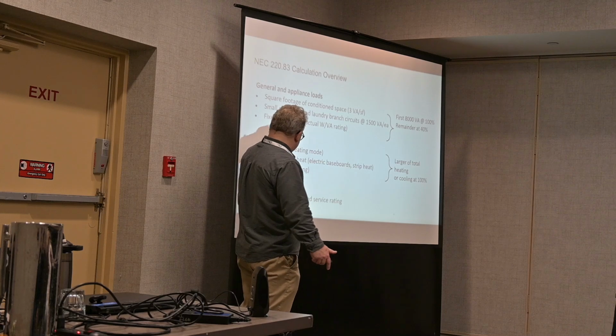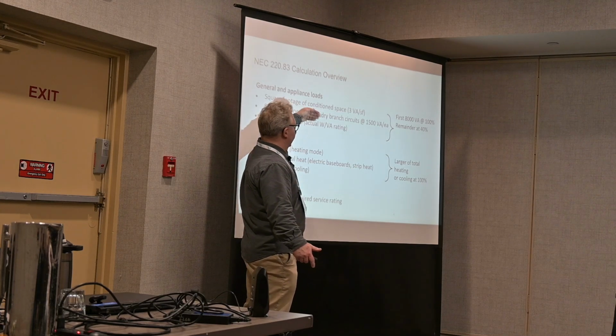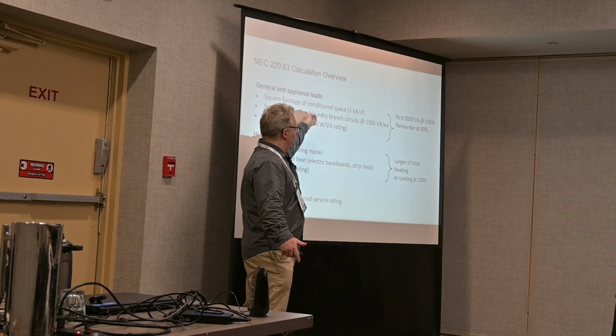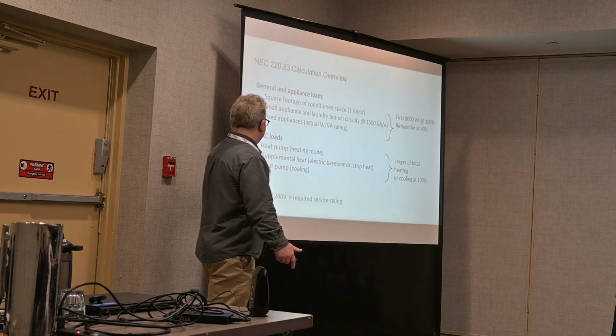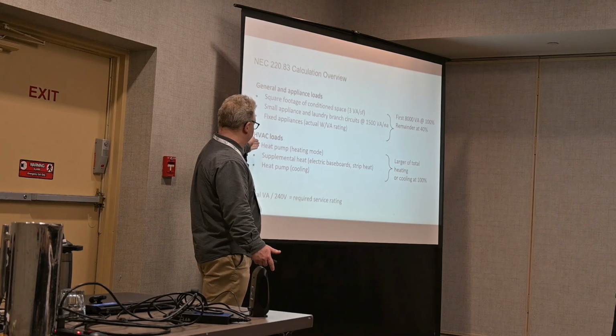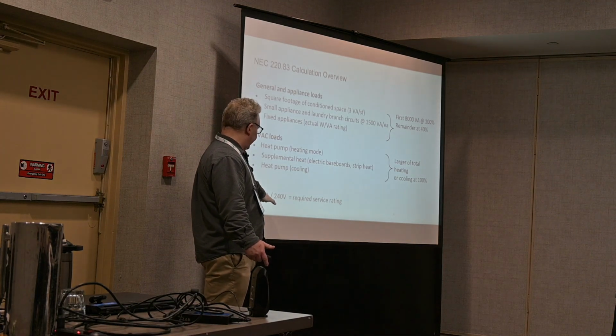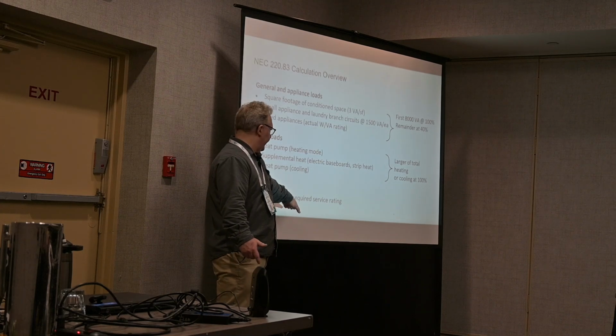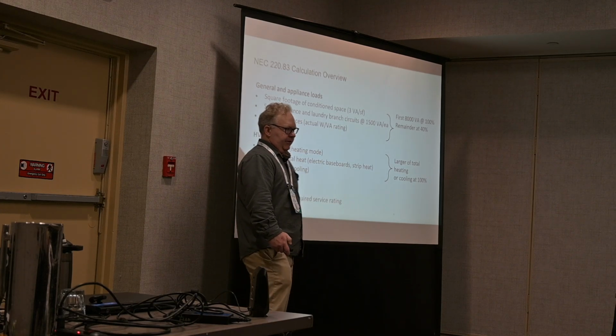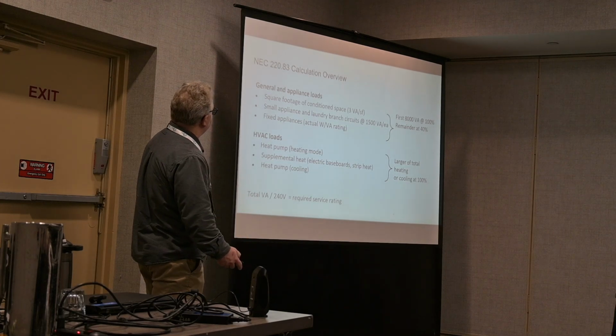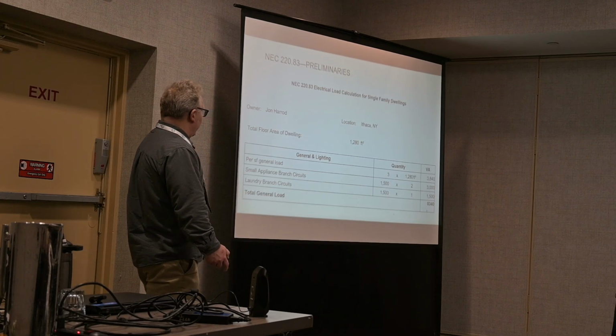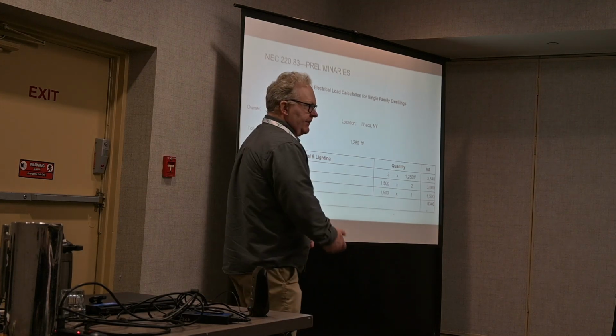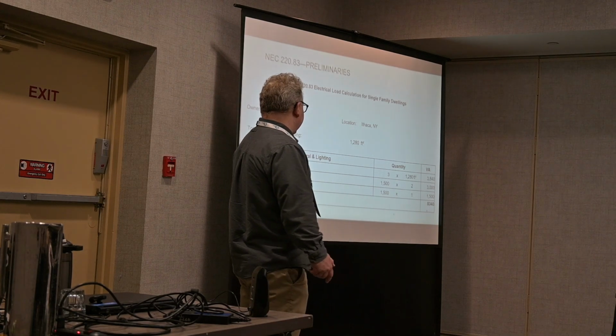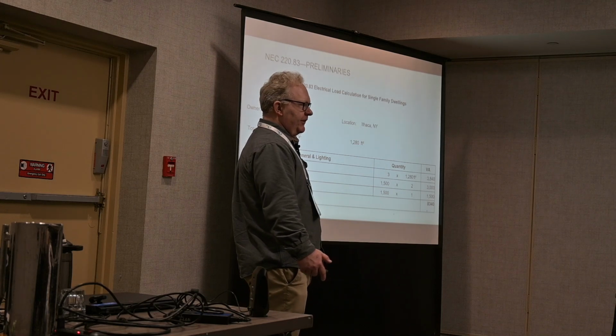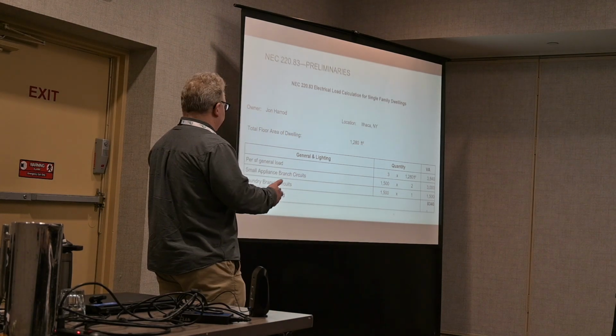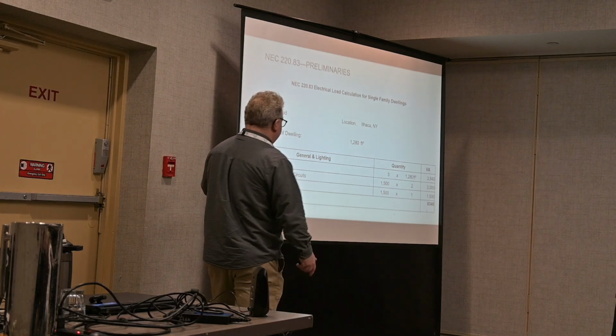And once you figure out the total adjusted volt amperes for your general appliance loads, plus the larger of your heating or cooling loads, you take the total volt amperes, divide it by 240 volts, and that gives you your required service rating. So what I'm going to walk you through is step by step how you go through this spreadsheet. It's about 4 slides of spreadsheet stuff, just to show you how quick these calculations can be if you have the right data. So this is for my own house.